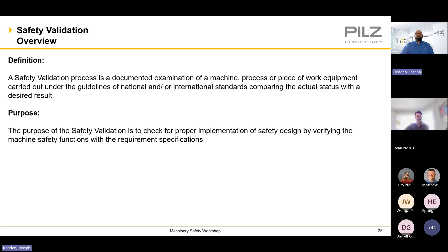Safety related control circuit examination: I look at my program, check my relays to make sure they're wired up correctly, test every switch, and hit every e-stop to make sure it sends the signal correctly.